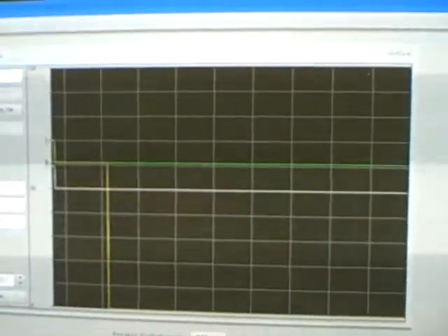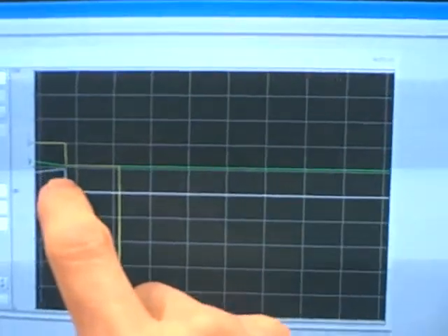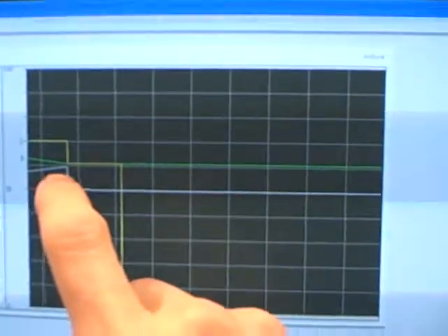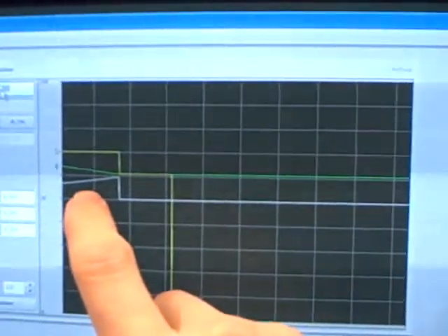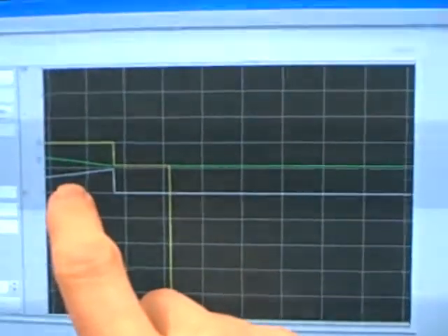I'm going to give it a new set point value, let's say 70%, and we'll see how the process responds. The set point steps up. The valve begins on an upward step. That's the way it's adding more liquid to the tank. The valve position begins to close as the liquid level rises. This is precisely what we expect from reverse acting proportional only control.